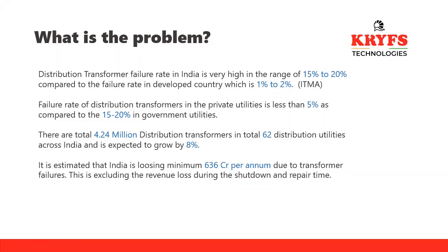In India, there are around 4.24 million distribution transformers, across 62 distribution utilities in total, and it is expected to grow by 8%. So the number of transformers is going to increase, and similarly the loss which is happening because of transformer failure is also growing. As we are adding new transformers to the fleet, we need to add more good and smart transformers so that we reduce the failure rate. It is estimated that India is losing a minimum of 636 crore per annum due to distribution transformer failures. This is excluding the revenue loss during the shutdown and repair time. It is only the cost of the asset.